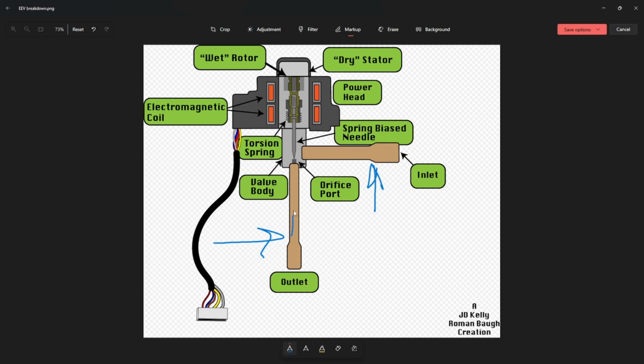So from stepper motor inlet to evaporator coil inlet, you would take a temperature reading from here to here with this valve in full open position, and that would tell you if it's actually restricted. Because if it's not allowing proper refrigerant flow or your pressure doesn't come up when the valve opens, that's another indicator that it's blocked up. So you would see a severe temperature drop from here to here if it's stuck shut or restricted. You would also see that our suction pressure never actually goes up, even though the valve may be reading open.